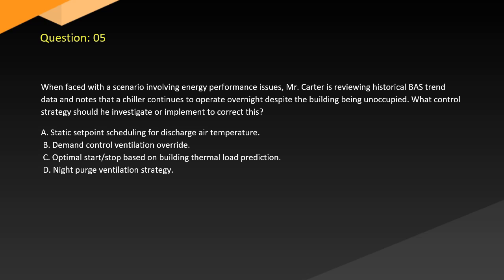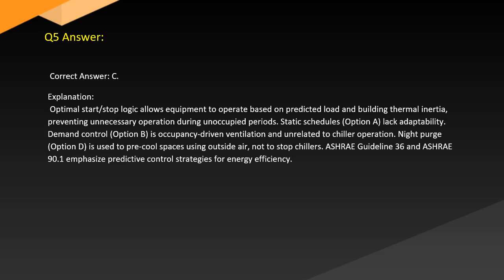A. Static setpoint scheduling for discharge air temperature. B. Demand control ventilation override. C. Optimal start-stop based on building thermal load prediction. D. Night purge ventilation strategy. Answer. Correct answer: C. Explanation.